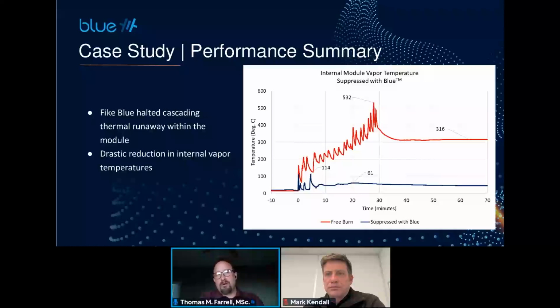One other point that's really important to note is, as compared to the free burn, by only allowing a certain number of cells to undergo thermal runaway, which happened essentially during the time that we allowed ourselves to fill that module, which takes a couple of minutes in this particular case, we were releasing those gases, but then we stopped. As soon as we stopped allowing cells to go into thermal runaway, we stopped generating gas. And that's really important for several reasons. One of those reasons is that if you have an active ventilation system, it would have to be a pretty high flow rate active ventilation system. But if you were using active ventilation, that in combination with blue would provide the opportunity to get things below the lower flammable limit for those exhaust gases inside of the ESS enclosure.